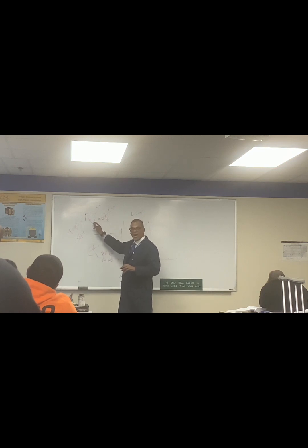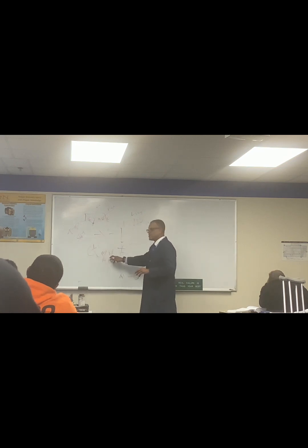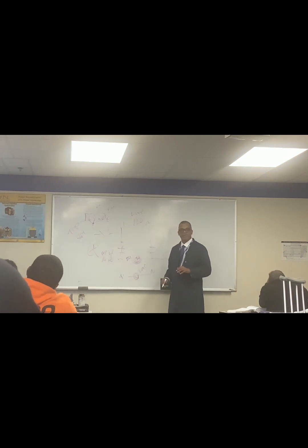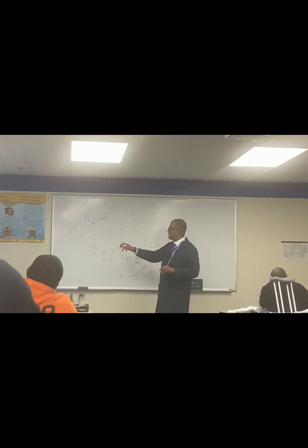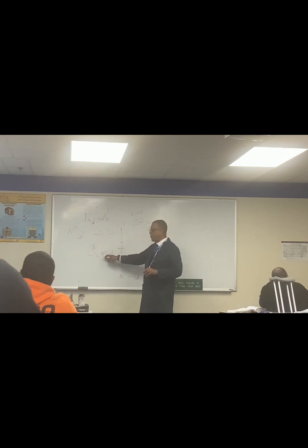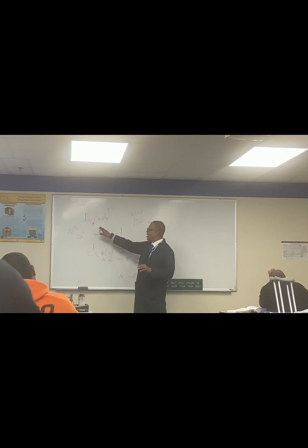R becomes Y when it starts to go out to the condenser. That is why you can jump R and yellow. It becomes Y, and so we can break it. It's a power leg. If we jump these two, they're the same thing, aren't they?